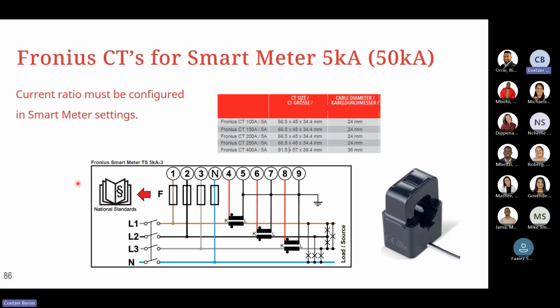With the Fronius CTs, if you're using a Fronius smart meter, we always recommend trying to use the Fronius CTs for the smart meter. If not, we recommend using a very high quality CT to make sure that the measurement values are correct. The current ratio must be configured in the smart meter settings itself when you are using a CT meter. Fronius recommends a max CT size of 400/5 when you are using the 5kA or 50kA smart meter variant. You can use larger CTs, but there are certain parameters and documentation that explain exactly how to use them.